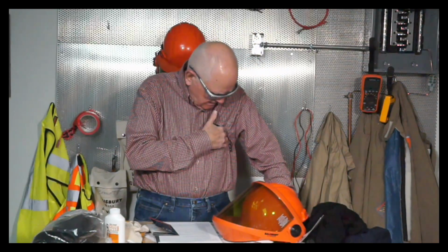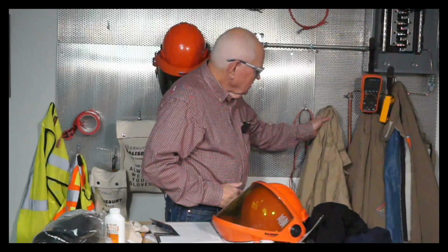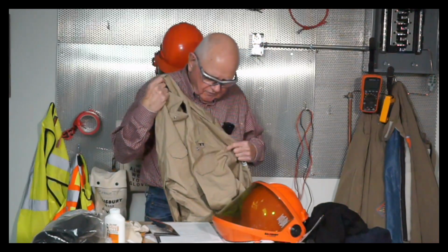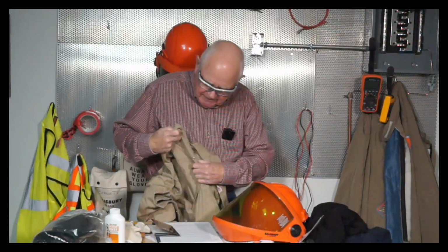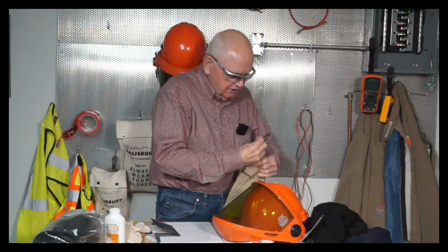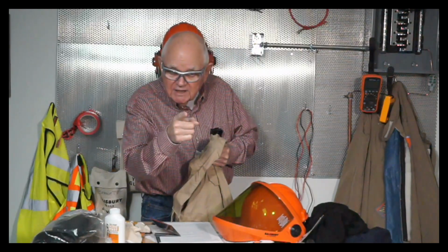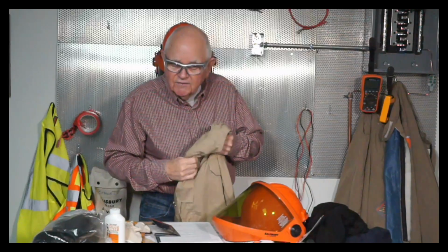This particular shirt that I'm wearing says Cat 2 somewhere. Yeah, it says Cat 2 on it. Cat 2, what does that mean? Absolutely nothing. Okay? Cat 2 is a term from the PPE category method: category 2 clothing must have a minimum arc rating of 8 calories, but that's not official. I actually look in the label on this shirt and it tells me it's rated for 8.9 calories. Oh, so I've got a little bit more protection than what that label says, huh? Well, no, that's not what I'm going to go on. Let's take, for example, a pair of coveralls. Somewhere on here it's got their Cat 2 label on it. So let's take a look and see. If I were using the PPE category method, I might say, well, these are good for category 2.